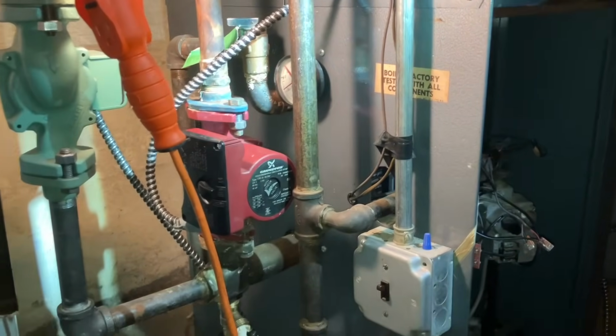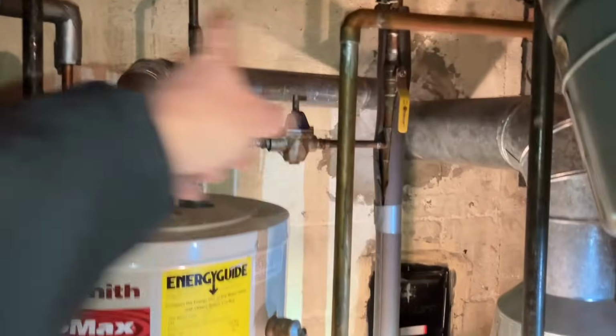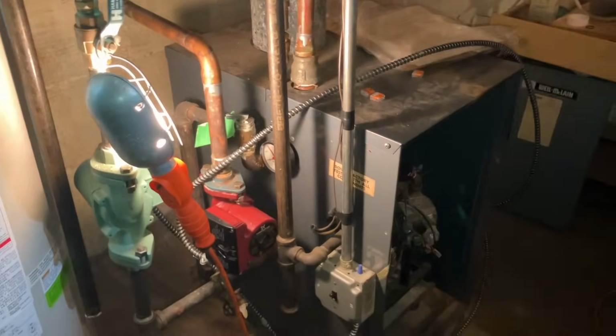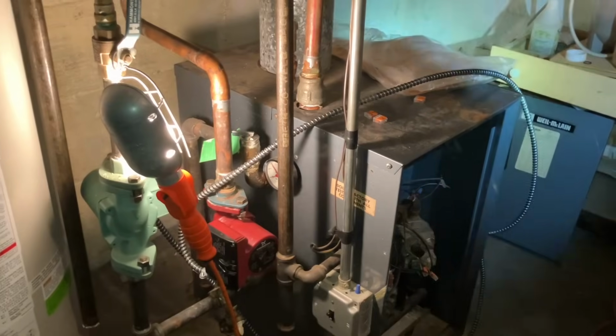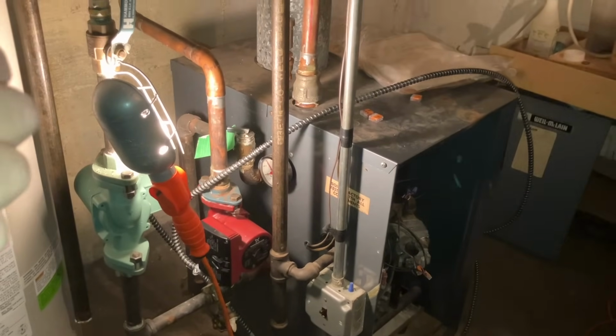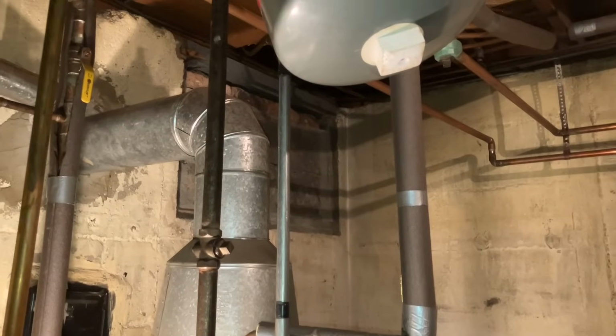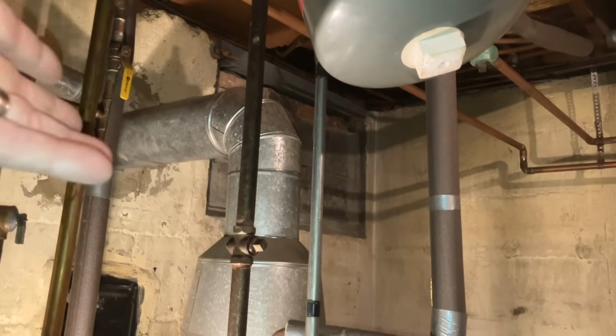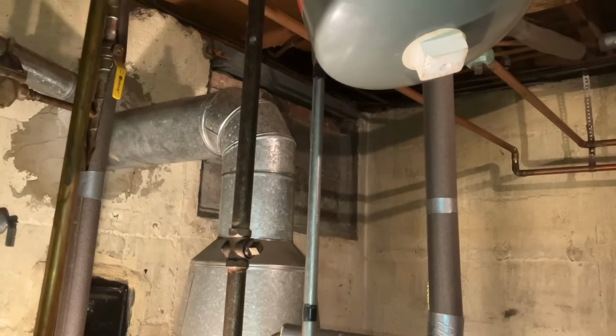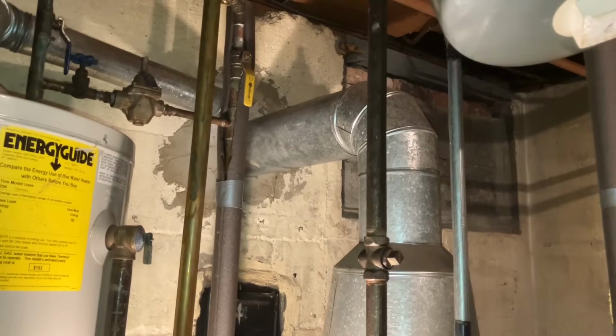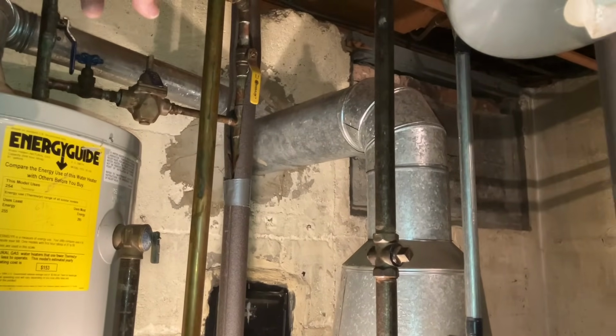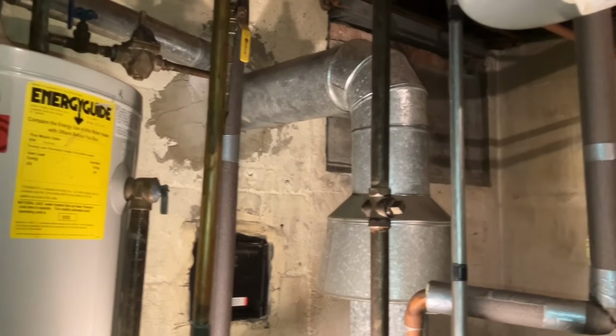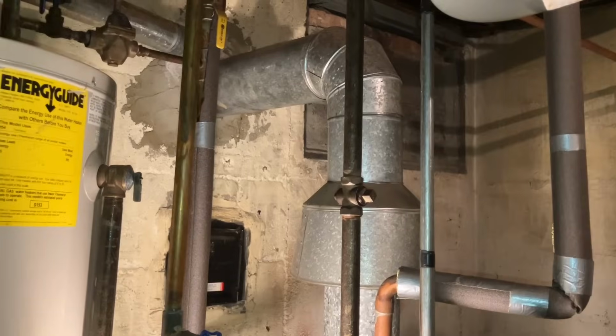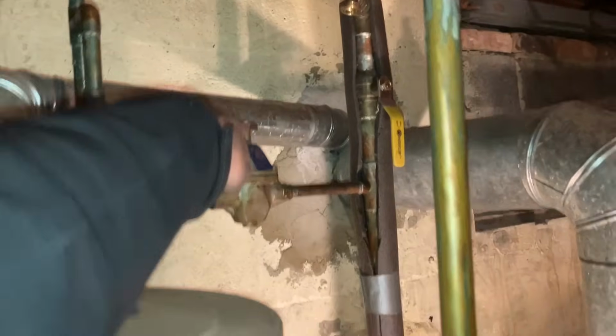But let me ask you a stupid question. Normally when I turn this off over the summer, it goes down below 10. And I always associated that with a malfunction in the way it works, circulating. Goes below 10? Yeah. Okay, so let's talk a couple things. Number one, we don't know how accurate the temperature and pressure gauge is. Number two, you have a 40-year-old expansion tank, which normally lasts 7 to 10 years. Right, so if you look at it the wrong way, it's going to just explode. I'm just joking. You have a pressure regulation device called the pressure reducing valve over there. That's also 40 plus years old. Be careful touching anything, because there's reasons why I don't like touching that lever there, because they start to leak.